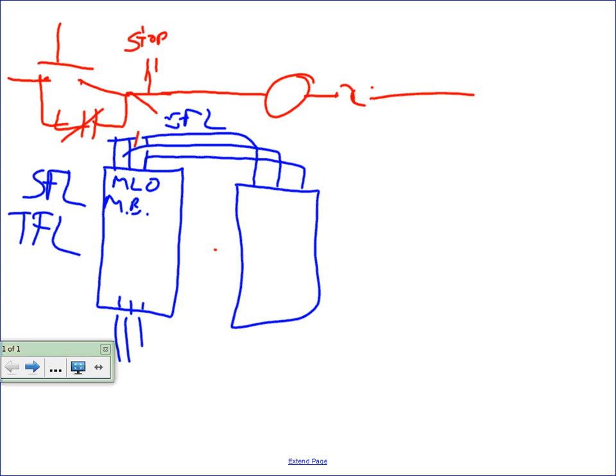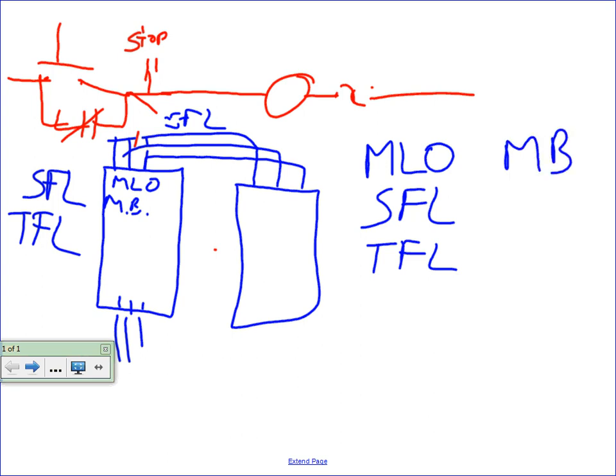It gets technical now. On main lug only panels, we can provide either sub-feed or through feed lugs. On main breakers, whatever lugs are on the breaker is what lugs you get. On a main breaker, we do not offer the sub-feed lug option. It's through feed only to get the second panel. And there are different times when you can use a main lug only panel and different times when you have to use the main breaker, okay?